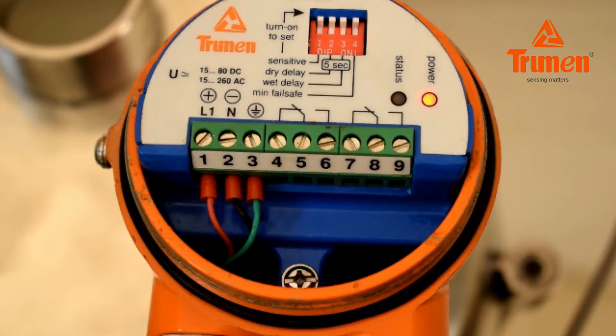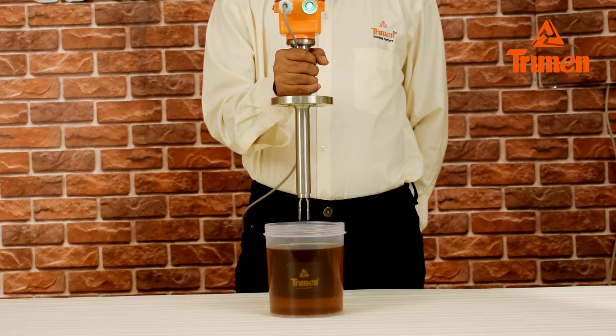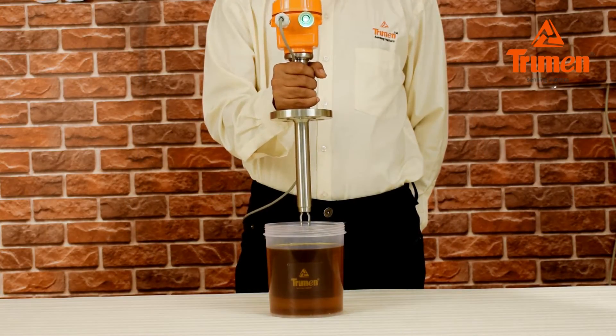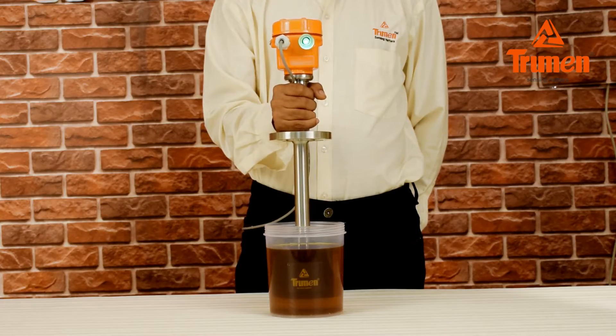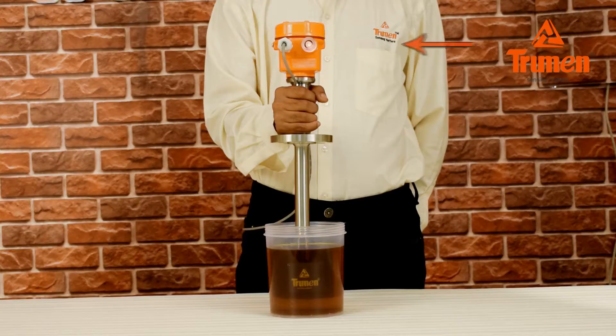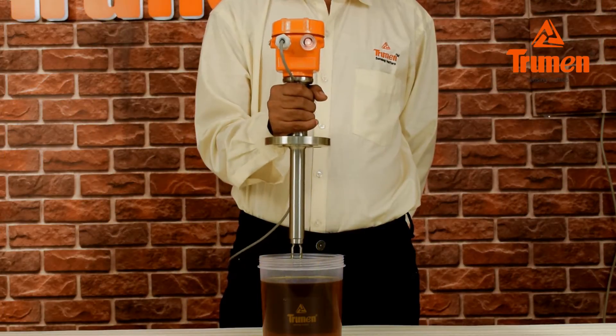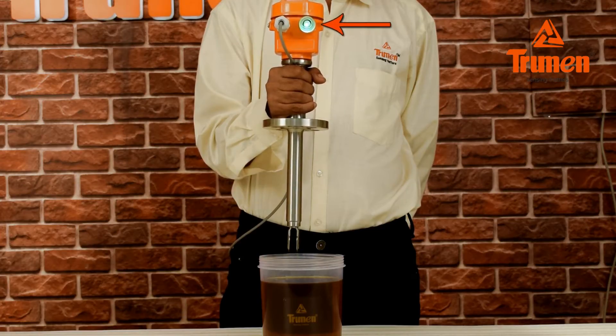Once powered on, the Trumen LFV starts vibrating in air — the power LED is on and the status LED is off. Now fill the liquid up to the fork tines level; you can see the status LED of the LFV turns on, meaning the liquid has reached the desired level. When the liquid is emptied, the status LED turns off, indicating the material has gone below the desired level.